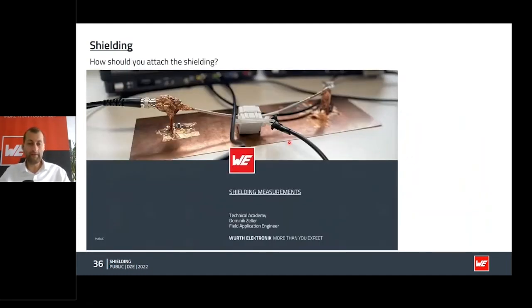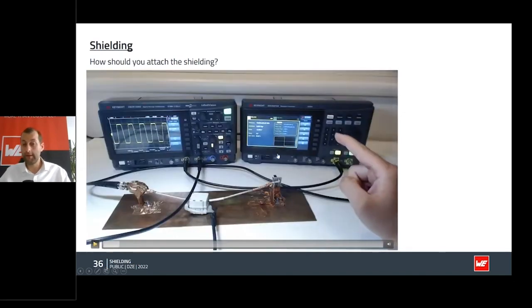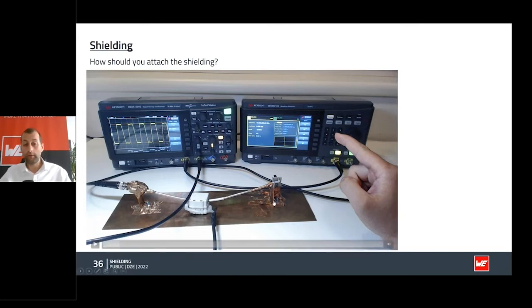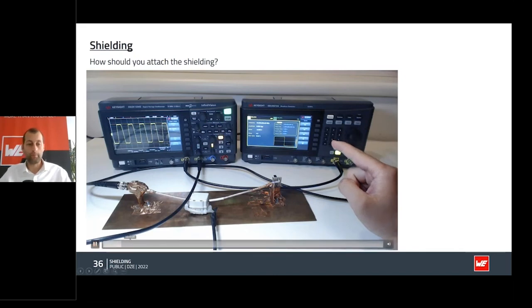I had customers in Austria who were failing the EMC test, and when they opened the shielding connection on one side they passed. So for the signal being shielded it is usually best to connect on both sides, but for the application it can sometimes be the opposite — so you are back in the trial-and-error phase, the so-called black magic of the electrical universe. In this measurement: the same setup — a square wave going through a coax cable, the inner conductor connected to a 50-ohm load, and on the cable a snap ferrite with some loops to catch the magnetic field.